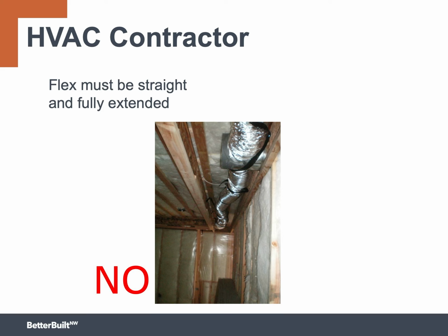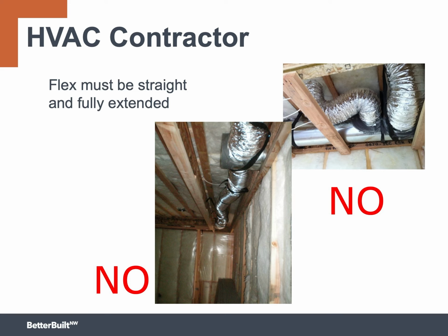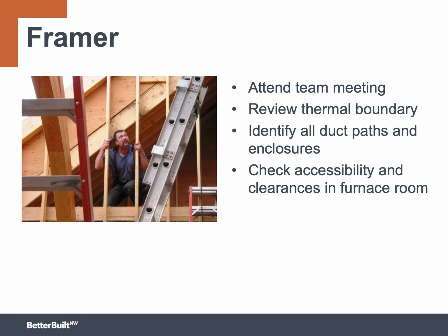In the field, there are many bad examples of flex duct that isn't installed very well and has created some real friction problems on the supply side of the system. Don't be afraid to cut the flex. The framer needs to attend the team meeting and pay particular attention to where the thermal boundary is. In many cases, framing is going to have to be in place to accommodate insulation and support the rigid air barrier material, and to identify all of the paths for the ducts and their enclosures.